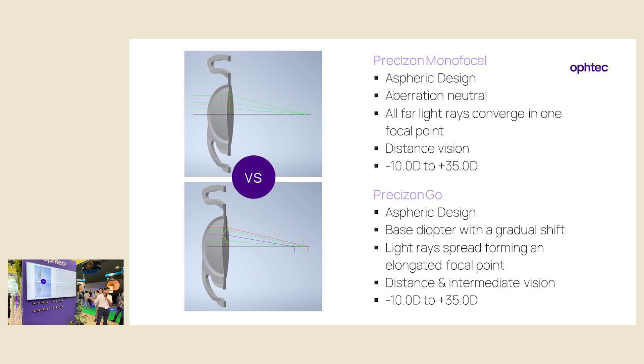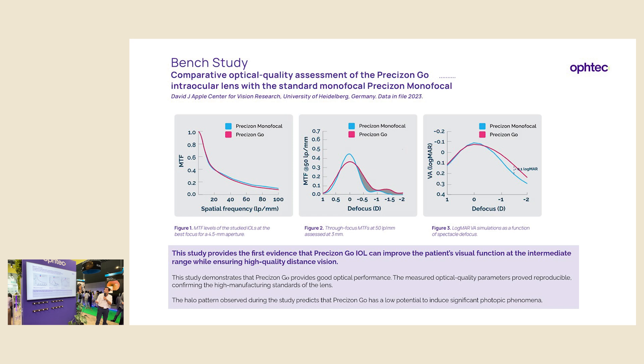The dioptric range is basically the same and very large, which is very good. An optical bench study shows that the optical quality of the image with Precizon Go is similar to the Precizon monofocal — the quality of optics and image is very good. At the same time, the defocus curve shows a flattening, demonstrating better performance at intermediate without compromising distance vision. This confirms that Precizon Go provides good optical performance in comparison to monofocals.